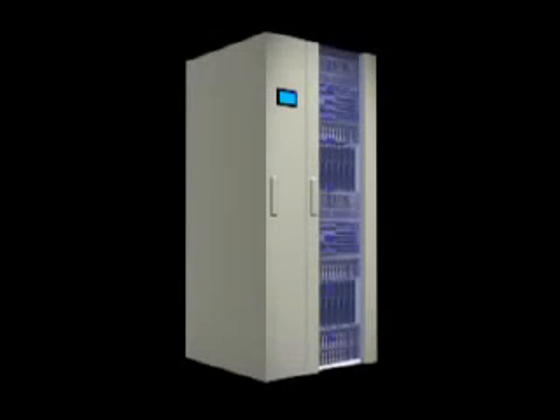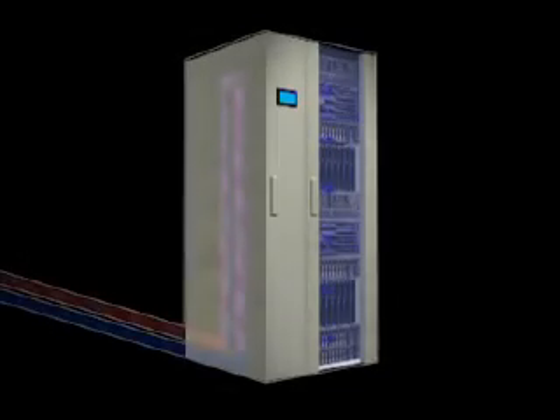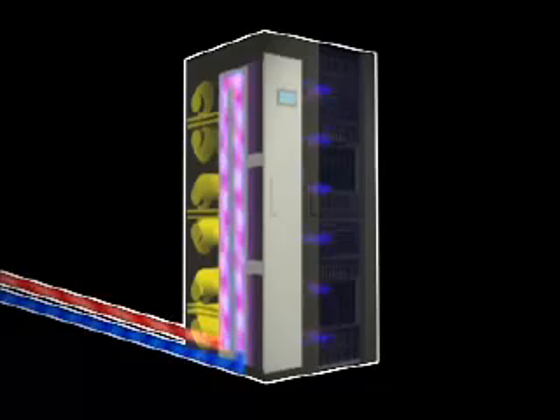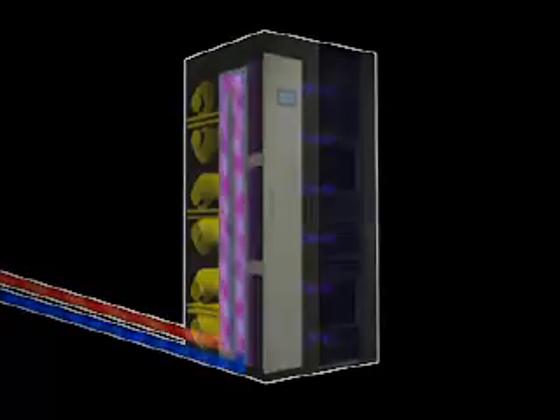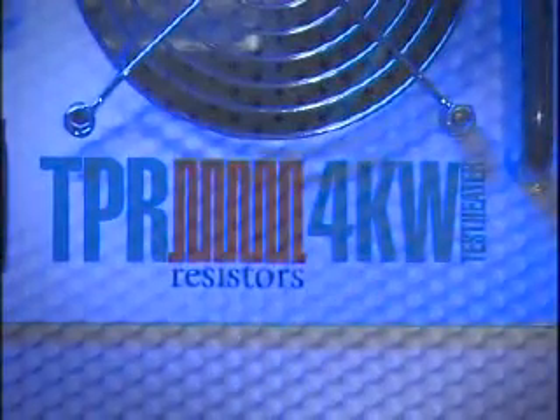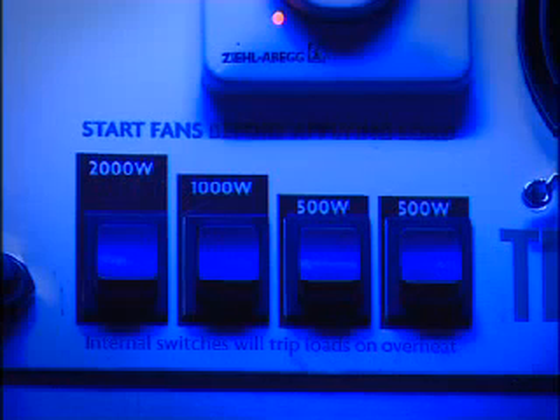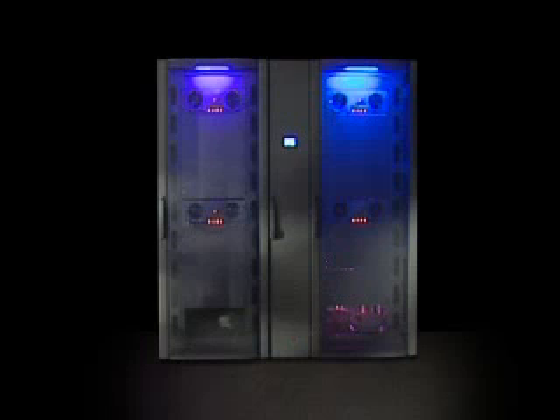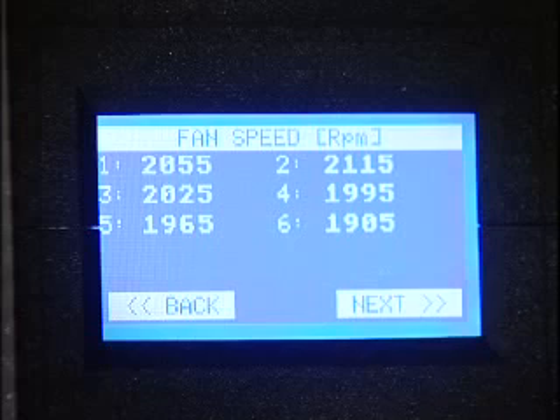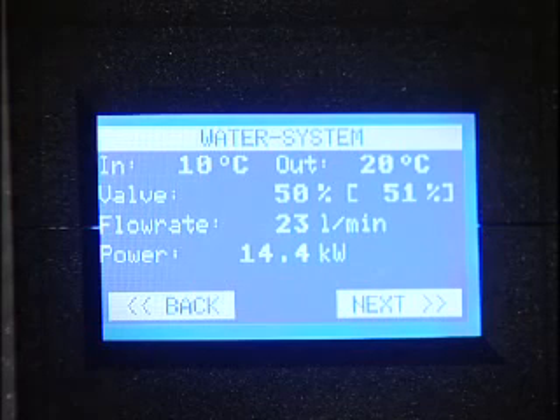Physically separating the hot and the cold air paths so they can never mix also significantly increases system efficiency. Water is generally readily available in most data centers, so installation of the LCP Plus can be as simple as connecting to your existing chiller circuits. With a greater efficiency than traditional open-loop systems, again the LCP Plus can give long-term financial gains. As can be seen in this demonstration, heat loads have been placed in the enclosure to mimic high-power blade servers. The heat load has been taken up to 20 kilowatts, and you can see the inlet and the outlet temperatures are stable.